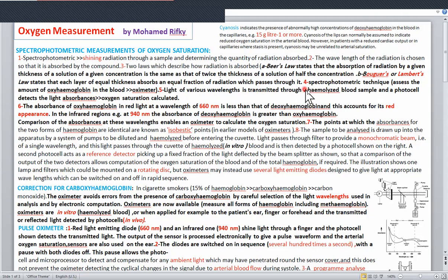The spectrophotometric method is based on differentiating between the two types of hemoglobin in the blood. This is why we call it an oximeter. First of all, the test is applied on hemolyzed blood to detect the absorption of the different types of hemoglobin. We always use two wavelengths.